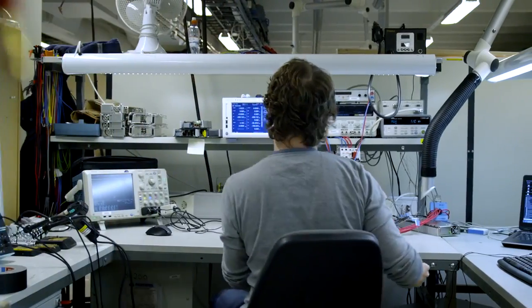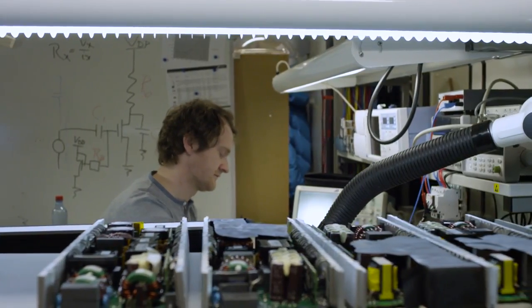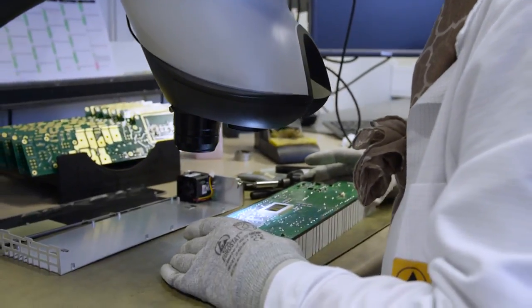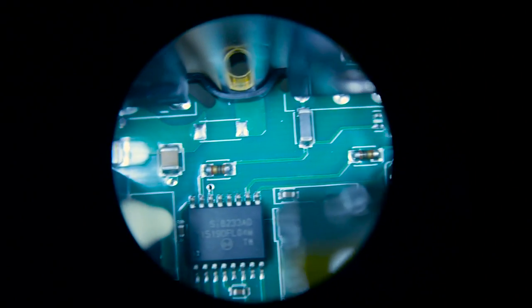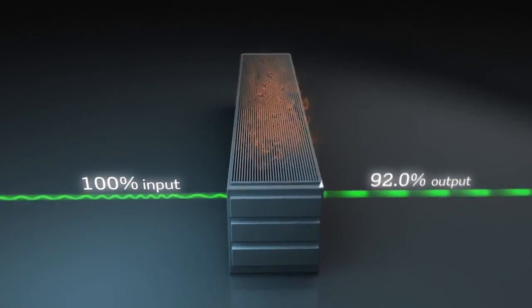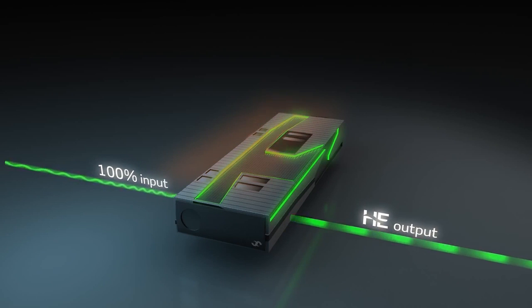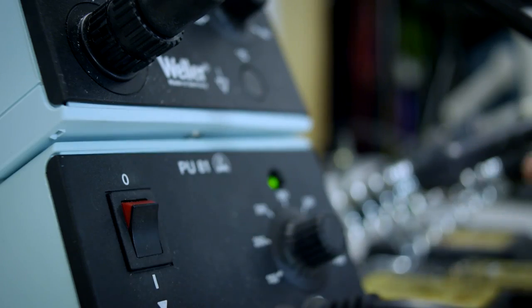It started with a project to design an inverter for a telecom system. Designing an inverter is a technical challenge in itself, but we were also required to design with high efficiency. The key for high efficiency is to use resonant topologies. So we decided to go for a resonant DC-DC converter inside the inverter. Naturally, we looked at the high efficiency technology used by Eltek in the Flatpack2 rectifiers. That turned out to be a rather complex design in itself, because in an inverter the power flow is in the reverse direction compared with the rectifier.